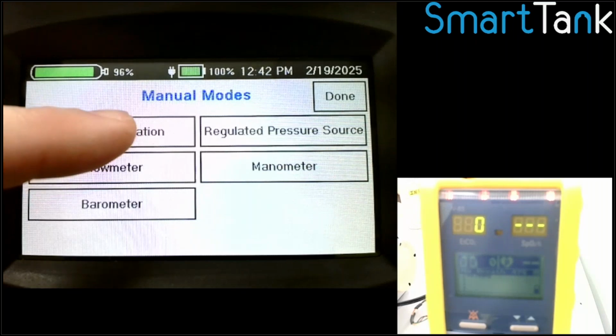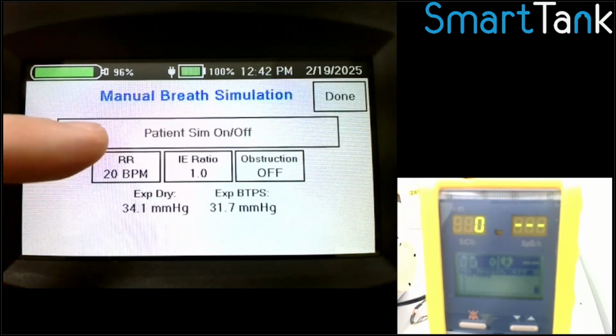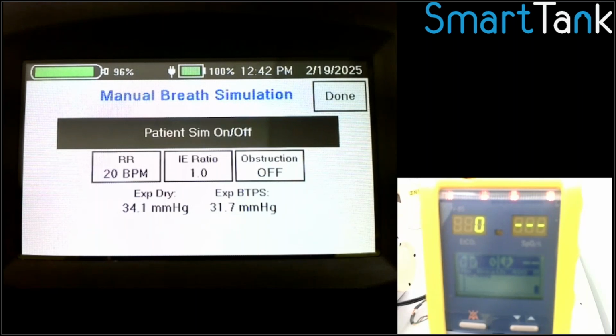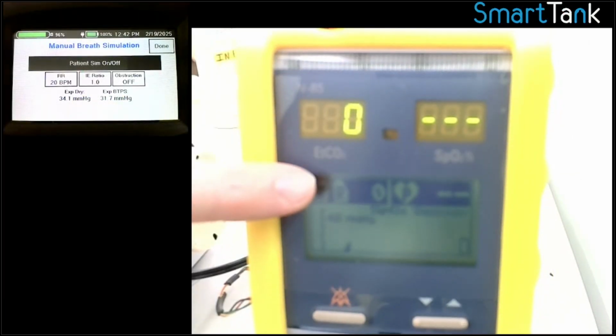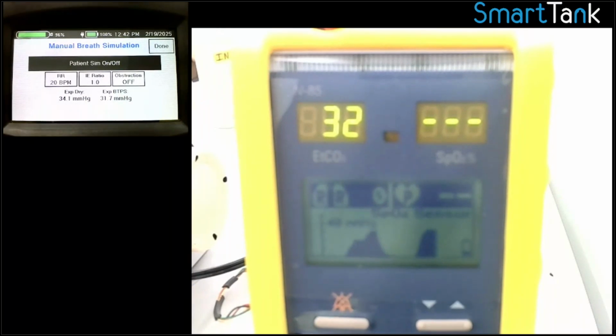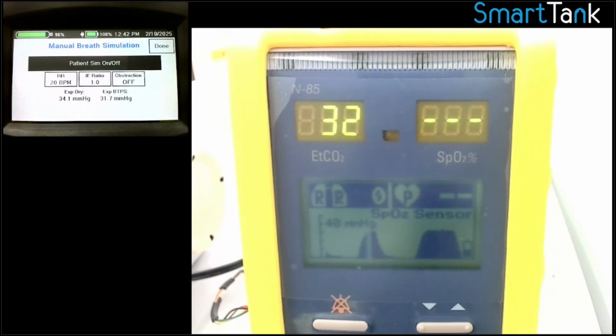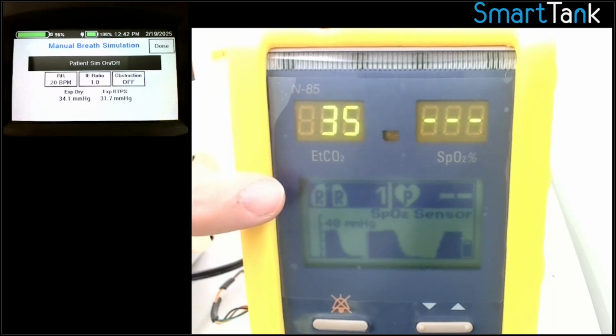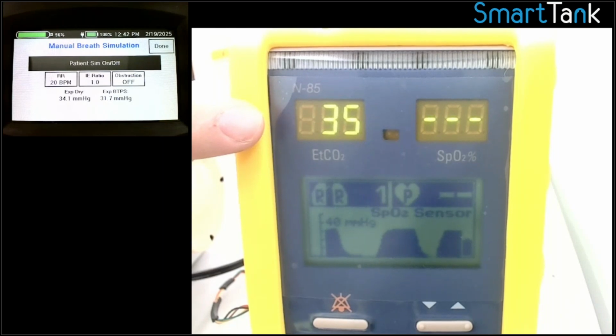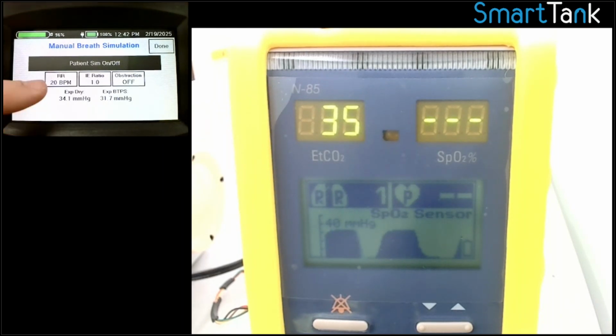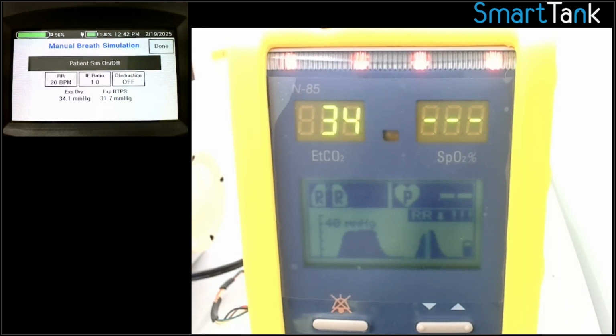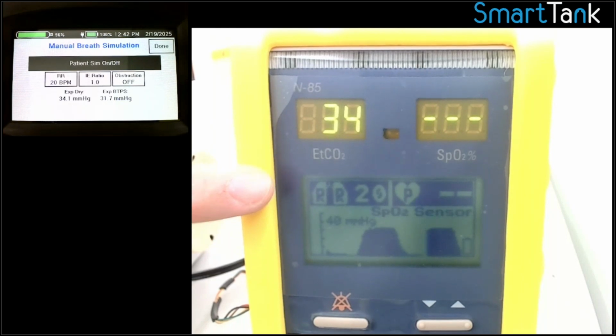So the last thing is this breath simulation. This is kind of nice if you want to go out and check something. I'm going to start this, and if you watch the yellow device over here, you'll see that the SmartTank will simulate a patient breathing. It will actually give you the respiratory rate here in a second as it comes up, and it will give you the end tidal value. If you look at the SmartTank, it's expecting 34 and 20 breaths per minute. And so there it goes. So 20 breaths per minute and 34.